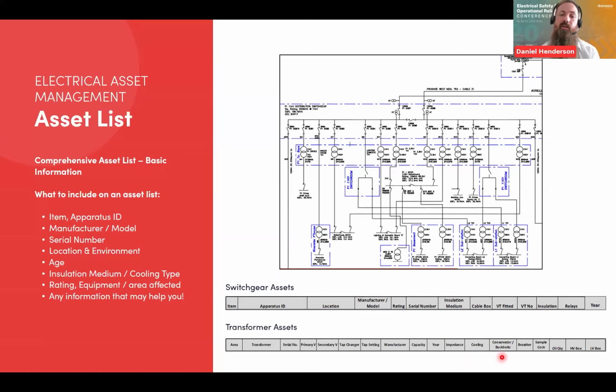Whether it has a conservator on it or not - some transformers have a tank elevated above them, known as the conservator. And if it does, it's likely to have a Buchholz relay in there from a protection side. This is information that will help us from a maintenance and planning perspective, especially knowing what assets we have and what we have to do in our maintenance.